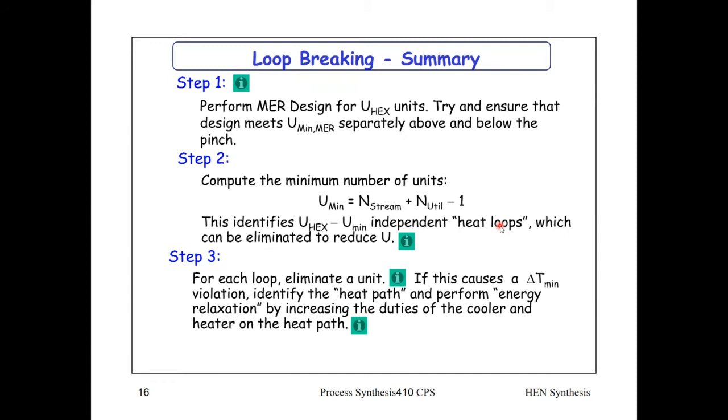You will have 3 different scenarios, 3 different designs. And the fewer heat exchangers you have, the less the capital costs, but the higher the running cost, because as you eliminate heat exchangers, you're reducing the capital cost, but you are using more steam. You're using more hot utility, which is the expensive one, and that will increase the running costs. So essentially, you can do those 3 designs and check which is going to be economically the most beneficial.